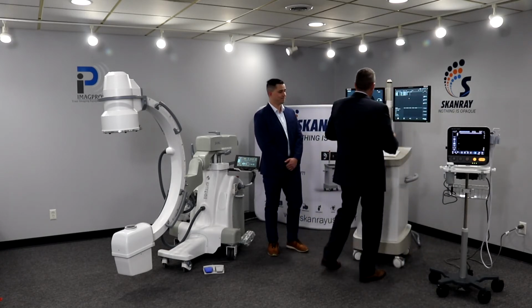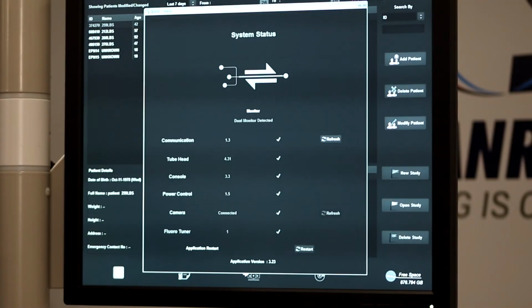So I want to hone in on the computer card. One of the features I really like on this system is it has a system status screen. It's called the Ready button. So every morning when you boot up the system, it will go through a self-diagnostics of the system. Every board in the system is listed here. If you ever have an X mark, it's going to tell you you have a communication problem, a tube head board problem, a console board problem. It's going to pinpoint the exact issue with the system.